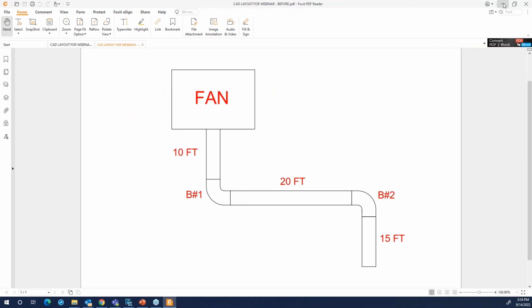ductwork and a bend. So typically you do not want to put a silencer right next to this fan. We have a lot of ductwork here we can work with. We can come back and say we can put a duct silencer here, or we can put a silencer here, or it might need two. We don't know, but technically you do not want to put one here. And a silencer should always be at least 2 feet after a bend if you're going to do that. Before a bend and after a bend, ASHRAE and SMACNA suggest very strongly that you have at least 2 feet of ductwork before or after the bend before inserting any type of silencer.